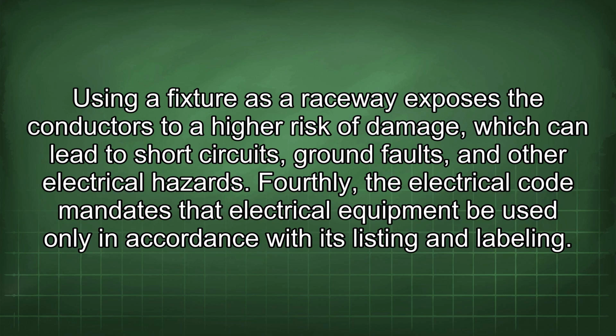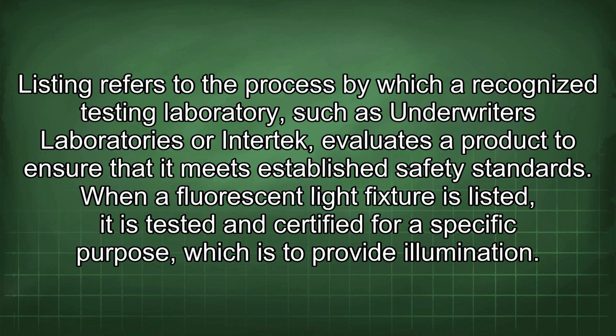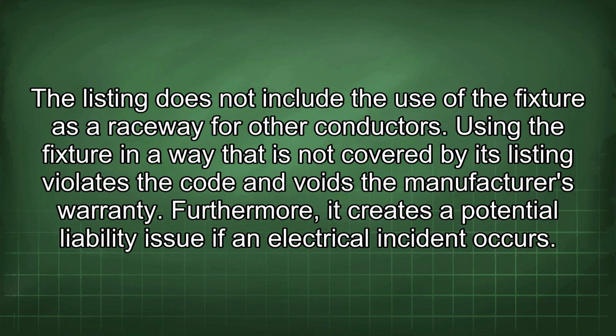Fourthly, the electrical code mandates that electrical equipment be used only in accordance with its listing and labeling. Listing refers to the process by which a recognized testing laboratory, such as Underwriters Laboratories or Intertek, evaluates a product to ensure that it meets established safety standards. When a fluorescent light fixture is listed, it is tested and certified for a specific purpose, which is to provide illumination. The listing does not include the use of the fixture as a raceway for other conductors. Using the fixture in a way that is not covered by its listing violates the code and voids the manufacturer's warranty. Furthermore, it creates a potential liability issue if an electrical incident occurs.